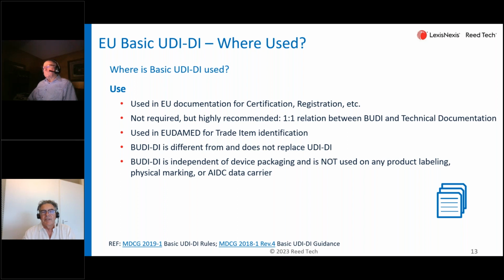The Basic UDI is not going to be used anywhere on the label or the packaging. And also changes in packaging do not impact the Basic UDI. But of course, you have your UDI. That is, of course, impacted by how you package your device. So different package configurations will lead to different UDIs on the label. So that's basically where you use it.